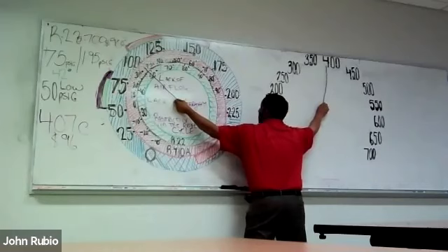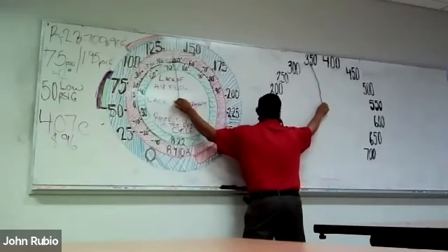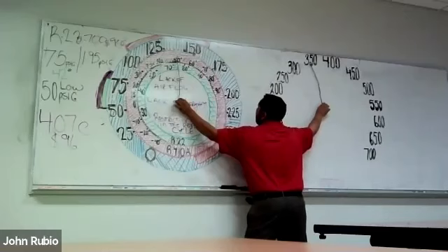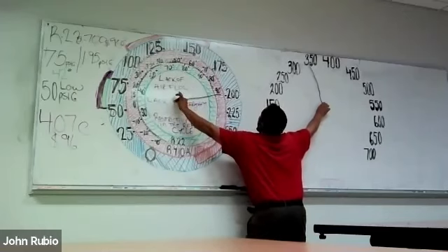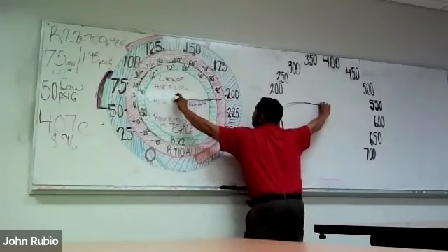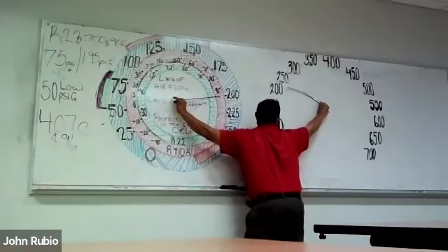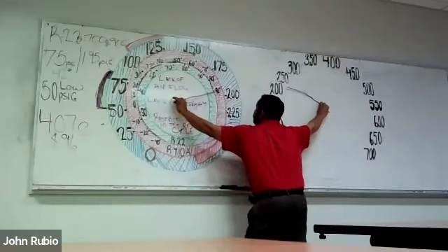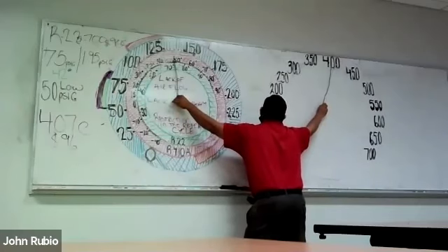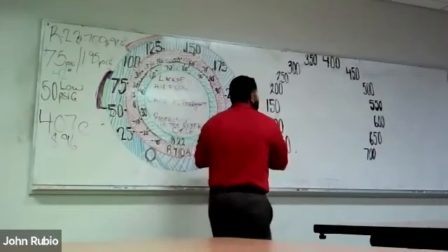They're slowly going to go back, but slowly. This is going to drop down, because this machine will not become properly equalized, 200 over 200, until the ice is thawed. You will only achieve equalized pressures of 200 over 200 when there's no ice on the coil. When you turn off your system and you're still metering, you're not going back to equalize. This is an indicator you have ice on the evaporator coil.